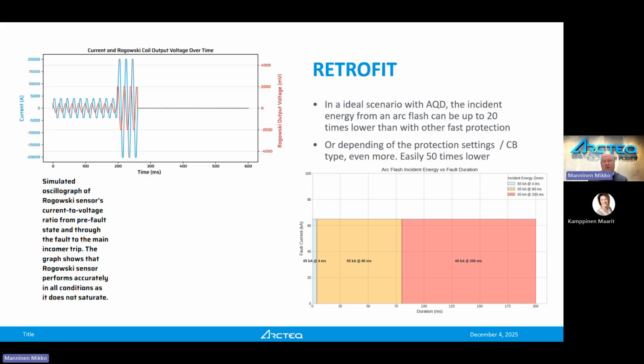Let me explain this a little bit. So also this is the retrofit part, because I just like to talk about it. So imagine that you have an older board, maybe some minimum oil breakers from that time, or it doesn't really matter. It can be actually even a new board, but the protection settings are with the longer delays, or the circuit breaker takes a bit more time. So this is just an example about the arc incident energy as a very much simplified calculation. So the y-axis, not that straight line here, but you get the point. The y-axis here is the magnitude of the fault, how much short circuit current and arc flash current we have in the fault. And the x-axis here, this is even worse. The x-axis here is the duration of the fault.